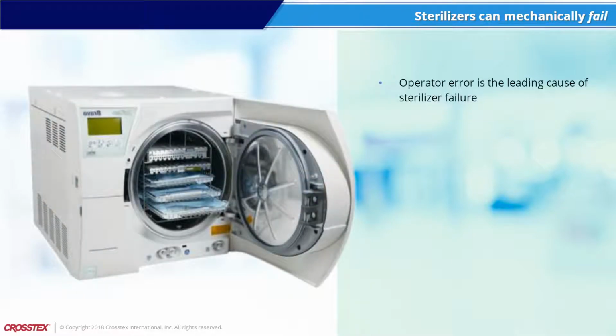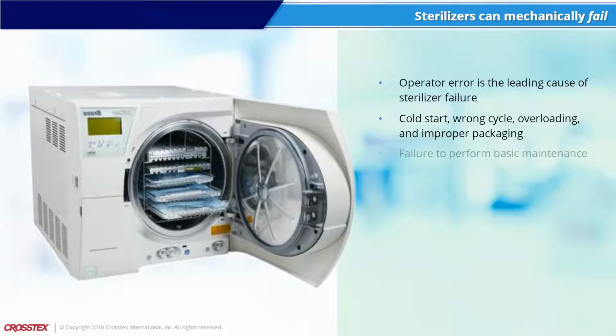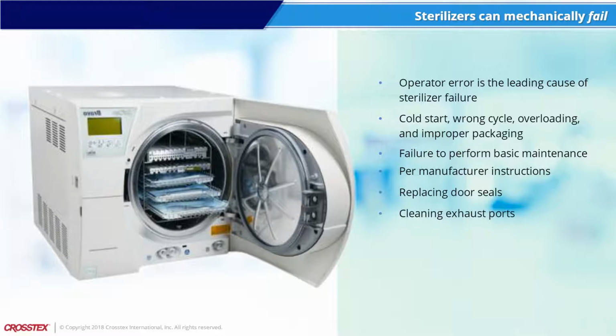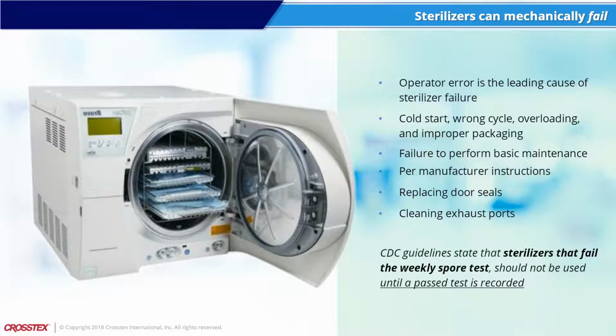While sterilizers can and do mechanically fail, operator error is the leading cause of sterilizer failure, i.e. cold start, wrong cycle, overloading, and improper packaging. Failure to perform basic maintenance per manufacturer instructions, such as replacing door seals, cleaning exhaust ports, etc., may also lead to mechanical failures. CDC guidelines state that sterilizers that fail the weekly spore test should not be used until a pass test is recorded.